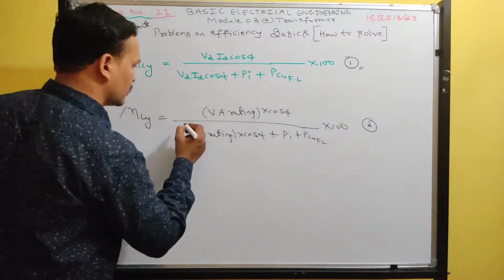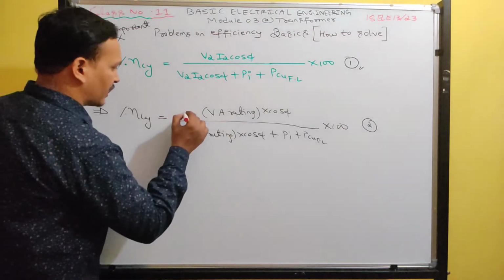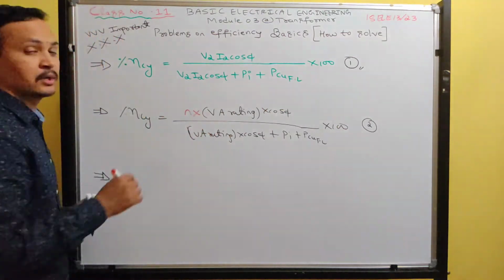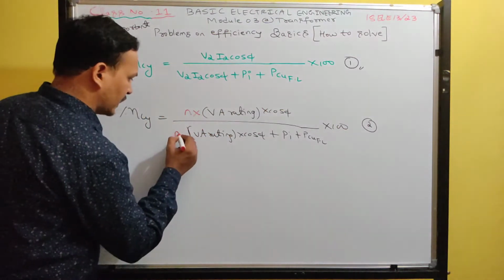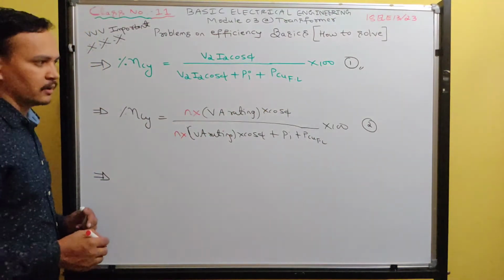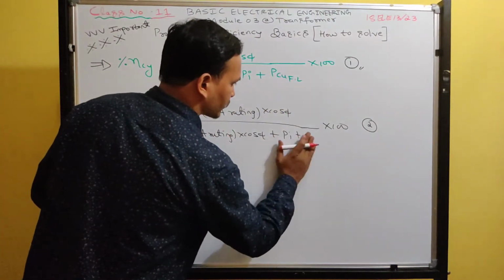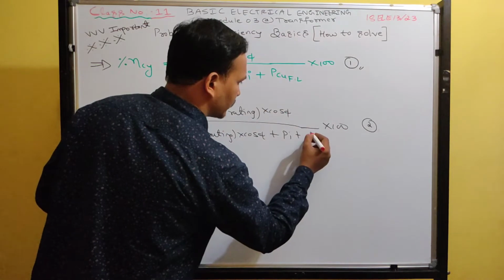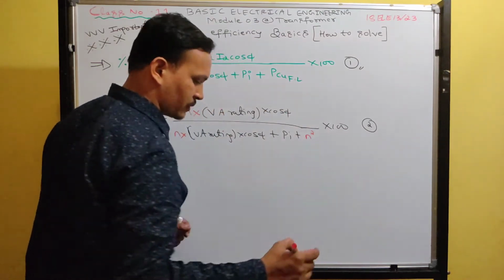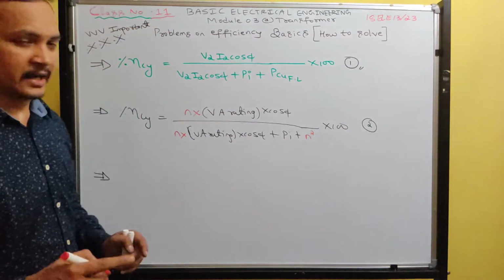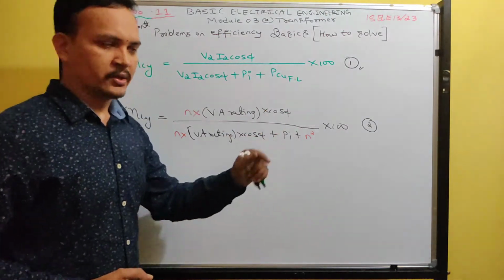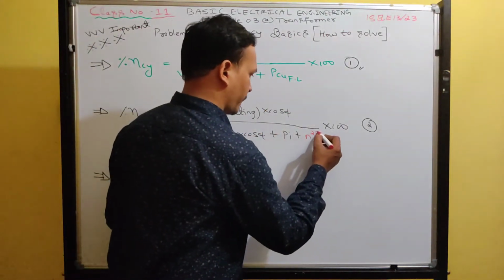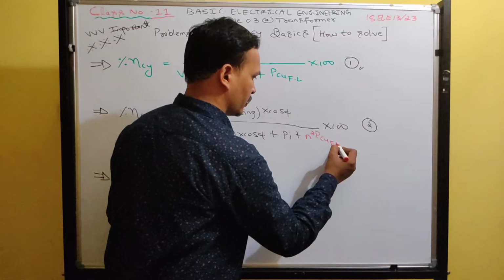Under such conditions, you must introduce a factor n, which is the loading factor. You write n into volt ampere rating, and in the copper loss term you write n square, because copper loss is I square R, current square, so the loading term also becomes squared: n square times PCU full load.